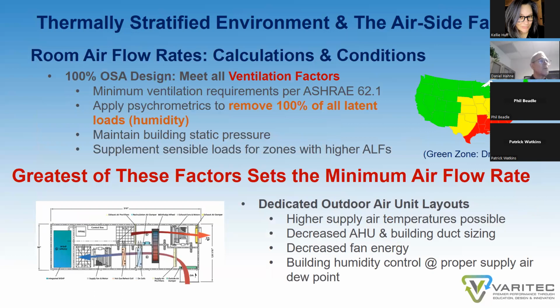So room airflow rates, calculations, and conditions. How do we know how much air to bring into the space? Well, first of all, we need to make sure that we meet the minimum ventilation requirements per ASHRAE 62. We need to apply psychrometrics to remove 100% of all latent loads within the building because the outside air is your humidity control factor. We need to make sure we have enough airflow to maintain building static pressure of 0.01 inches positive, and then to handle any supplemental sensible loads for zones with higher ALFs. Whichever is greatest of these factors will set the minimum airflow rate to a building. So that is a good guideline to understand how much airflow you should use.